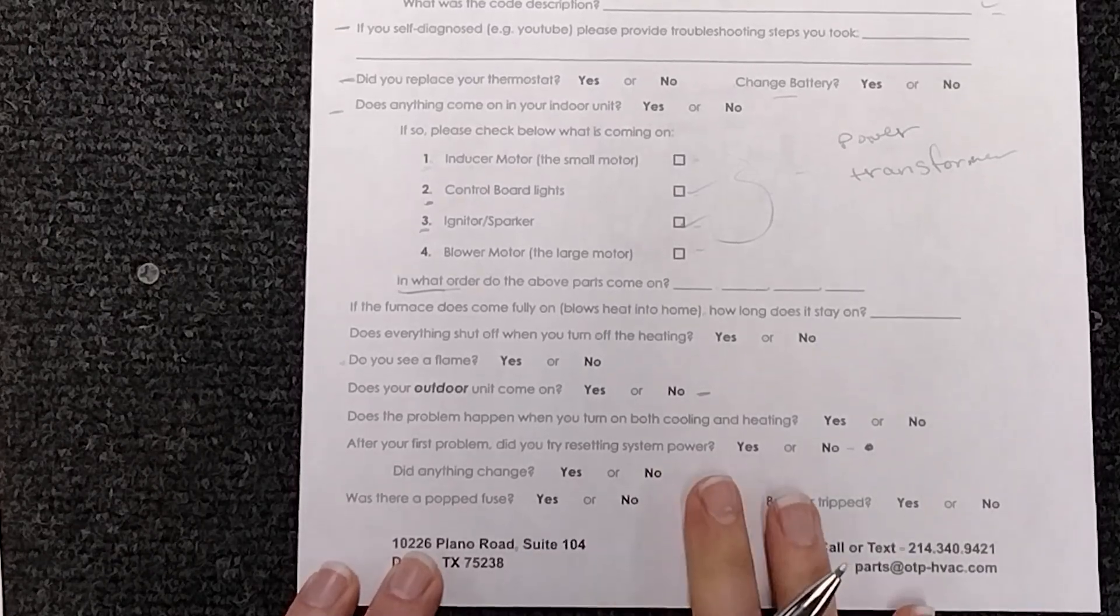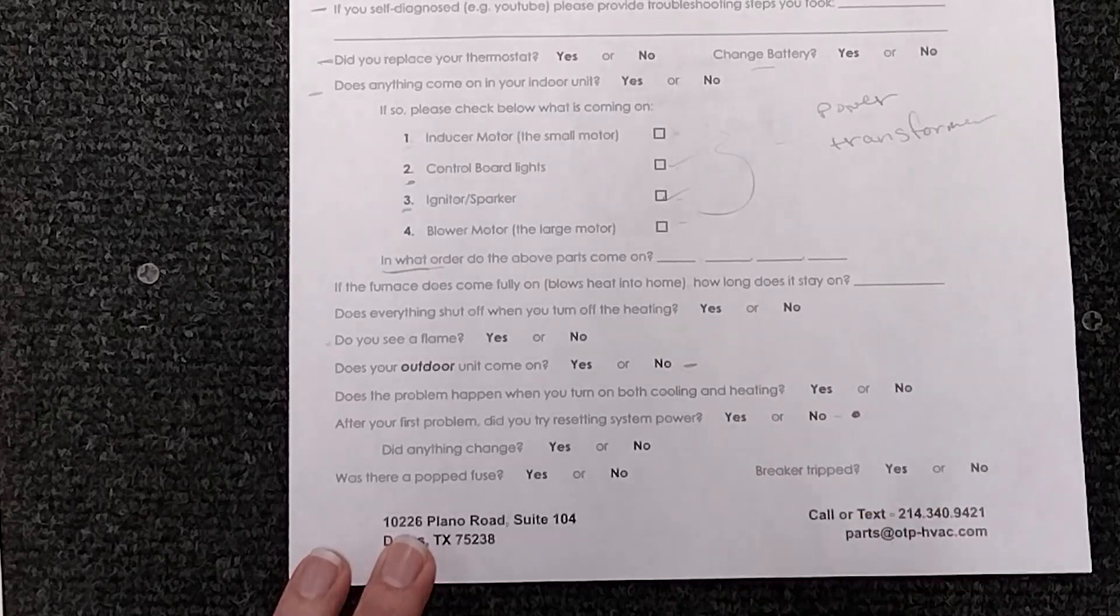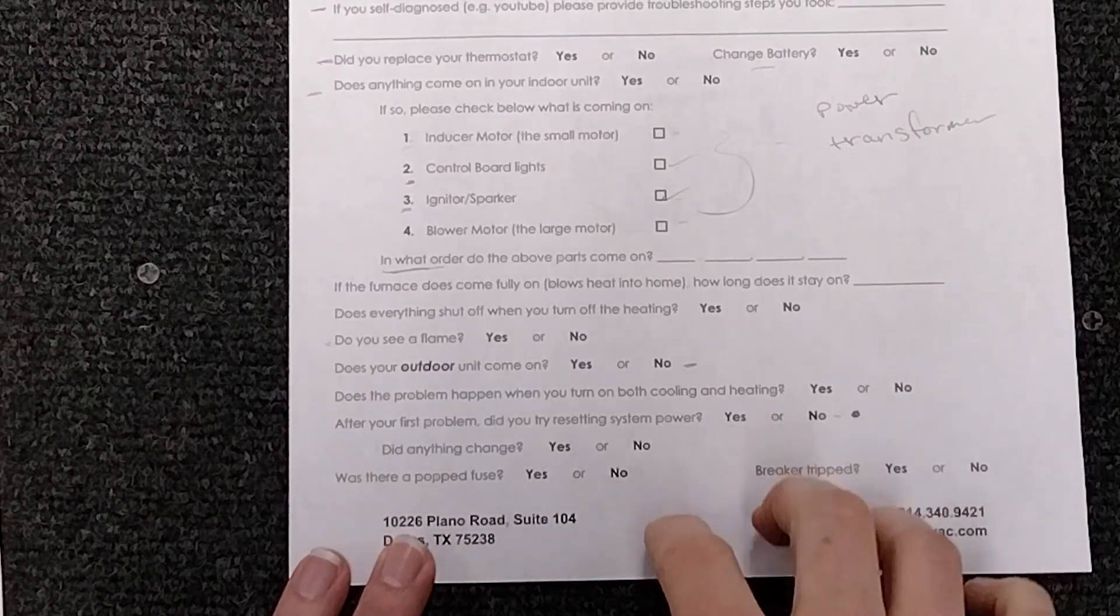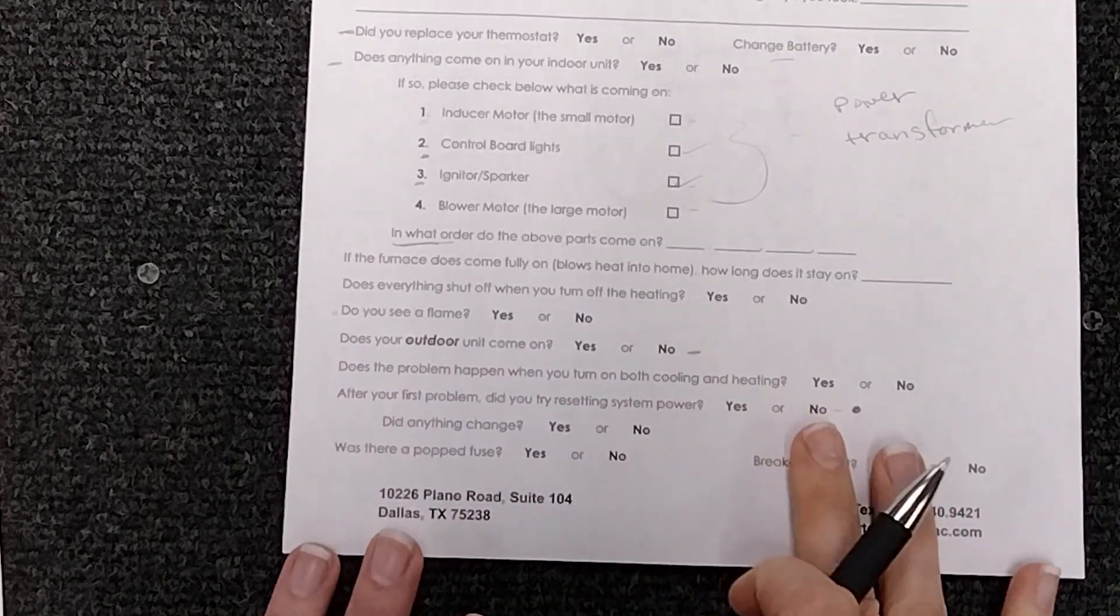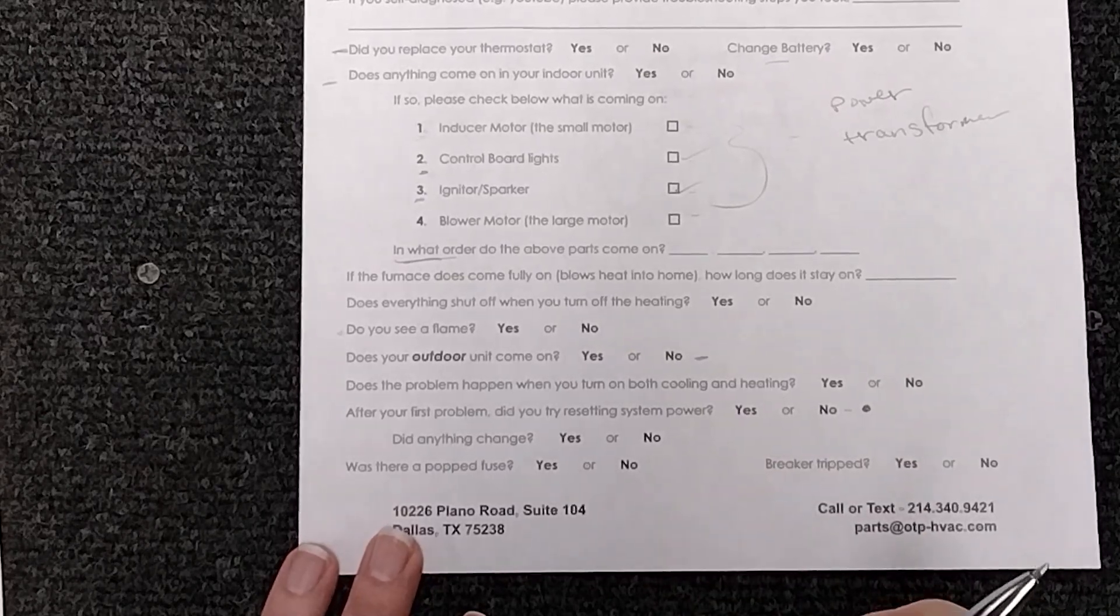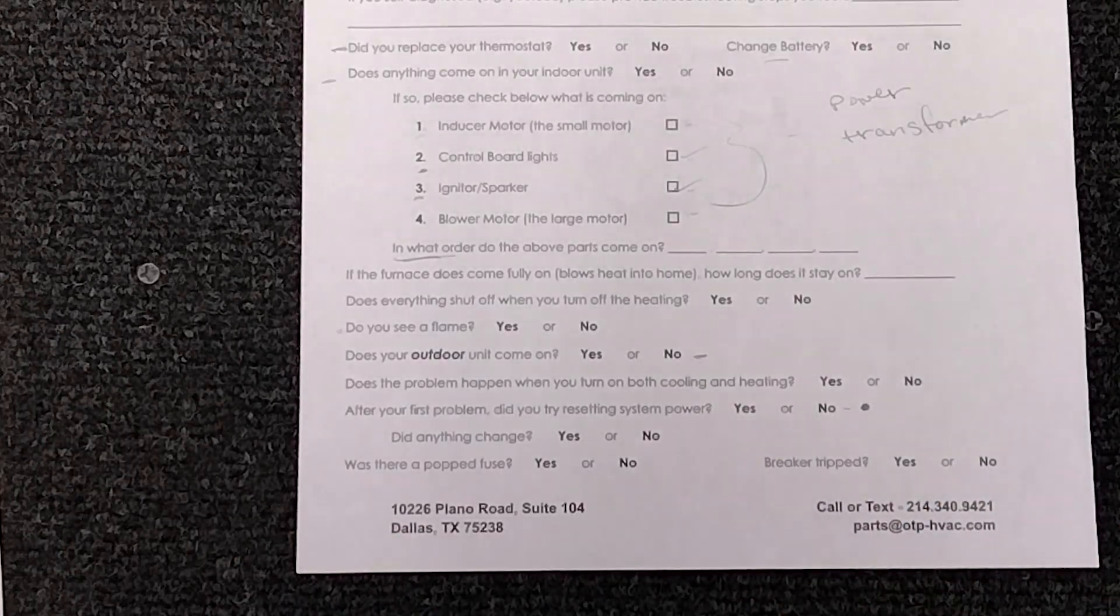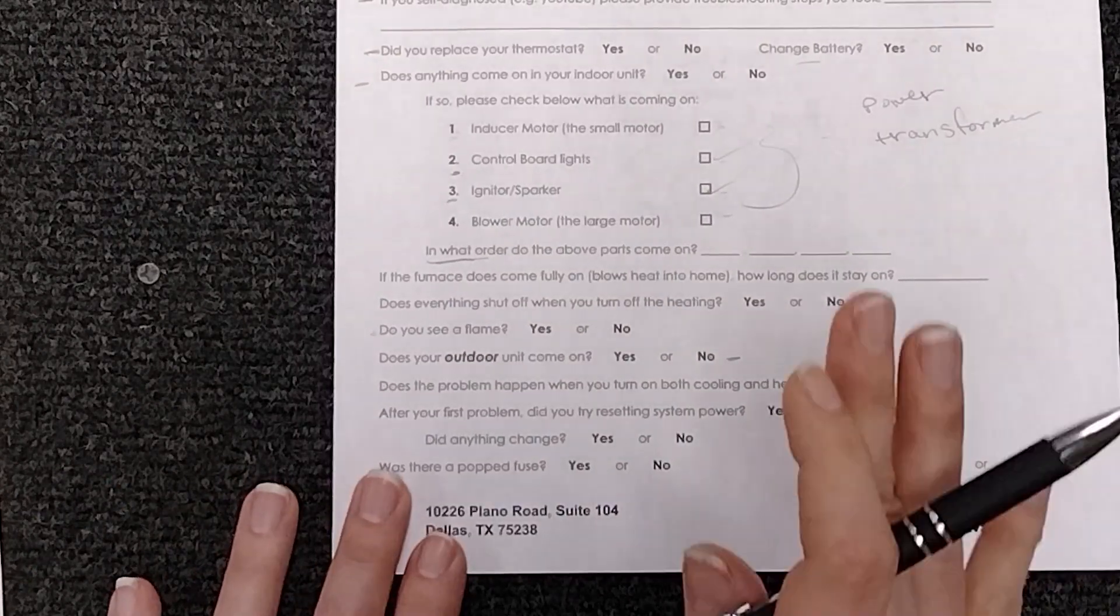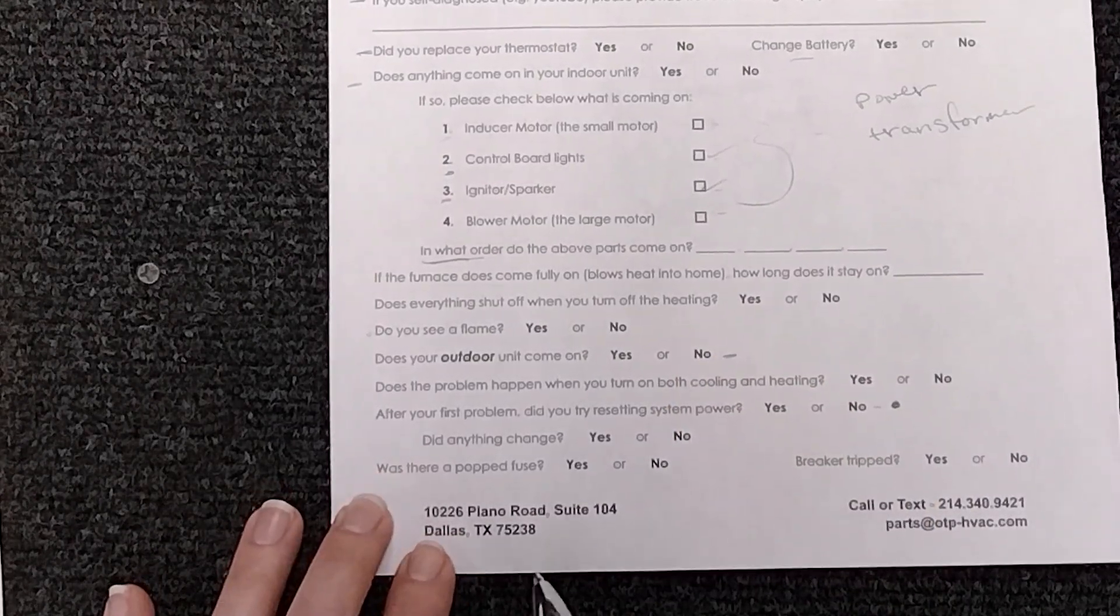So another and this sounds so dumb but it is incredible how many times I've had people have this issue is well I've already reset the power. Do I need to reset the power again? Yes absolutely 100 percent. Put everything back together the way it was after you think you've fixed the problem. Or if you're still trying to diagnose it make sure you reset the power. And the reason behind that is it could still be in a lockout or purge mode. So say you put everything back together and immediately your blower motor and your inducer motor come on it's still in a purge cycle. So make sure you reset the power even if you think you've done it a million times. Just do it.